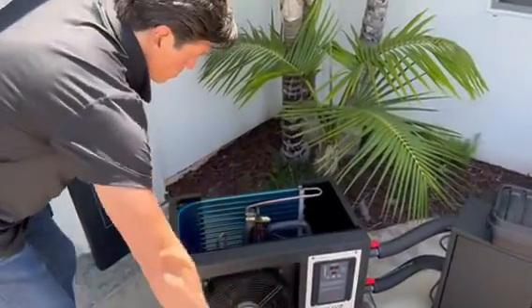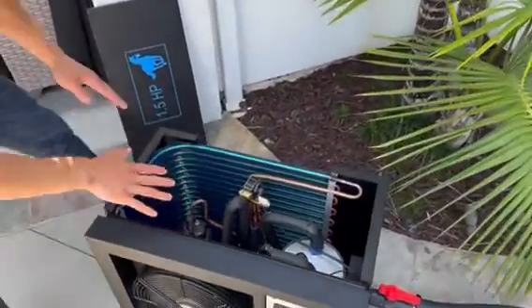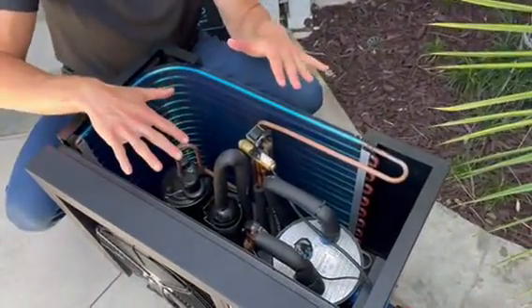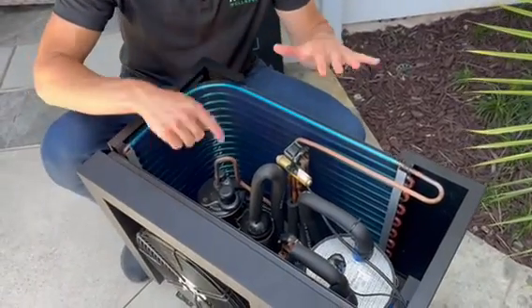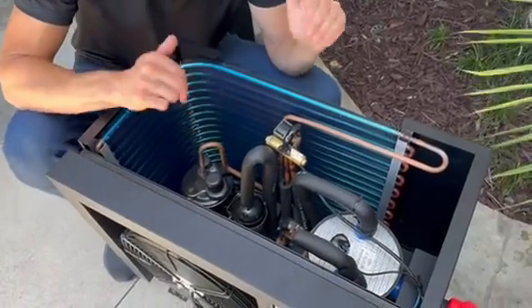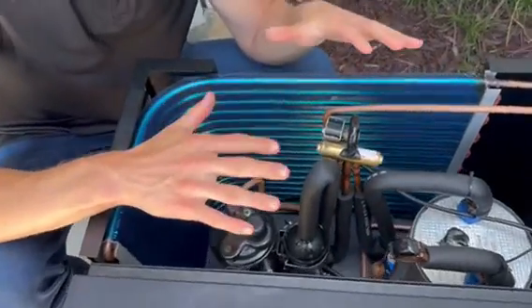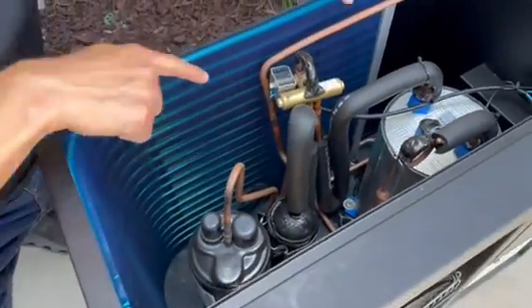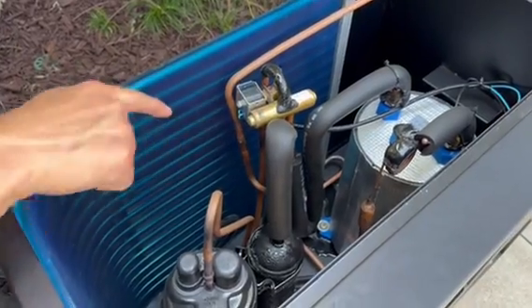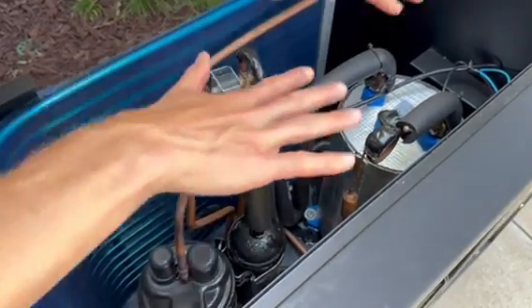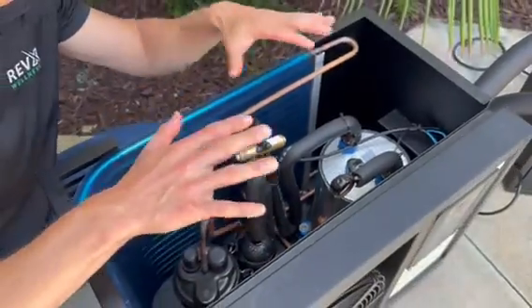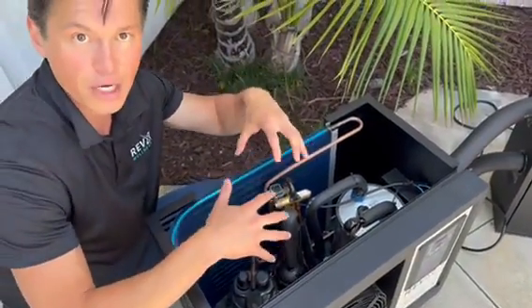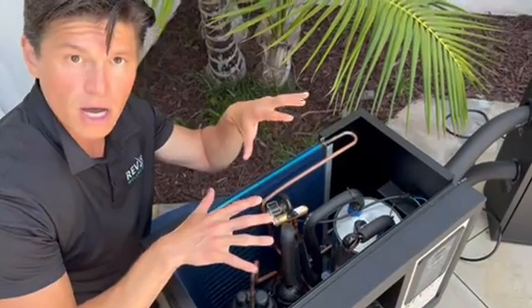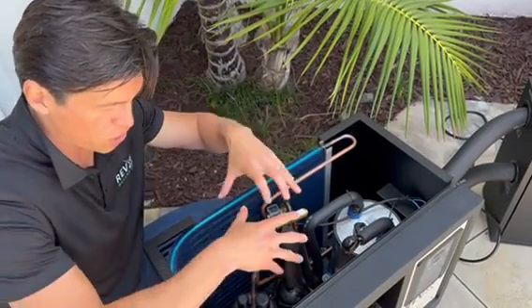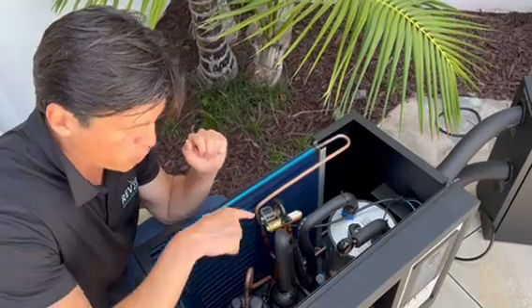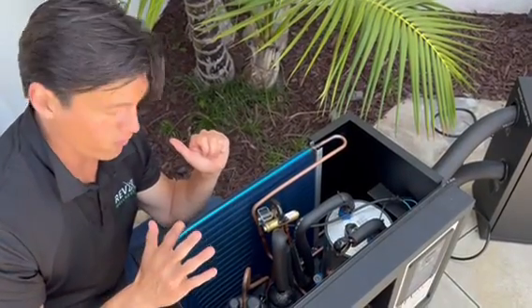Watch out, bud. And see if you can spot the vibration of where the noise is coming from. It's very important to pinpoint exactly where the problem is. Now, usually the problem is the copper pipes, so this is a copper pipe right here. By the way, it's really warm, so don't hold on to anything in here. While the chiller is operating, guys, do not put your fingers in here, okay? I can do it because I know the system really well, but you should not be just touching anything. So just observe and try to see where the noise is coming from.